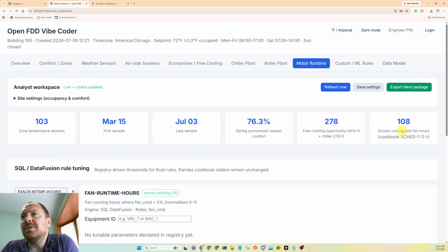There is some excessive run hours for the equipment because the client said per their lease they need to maintain 72 degrees with, I'm just saying, a 2-degree deadband up and down, Monday through Friday, 6 a.m. to 5 p.m., and Saturday, 7 to 2 p.m., closed on Sunday. So I'm coming up with 108 hours of excessive air handling unit equipment runtime.